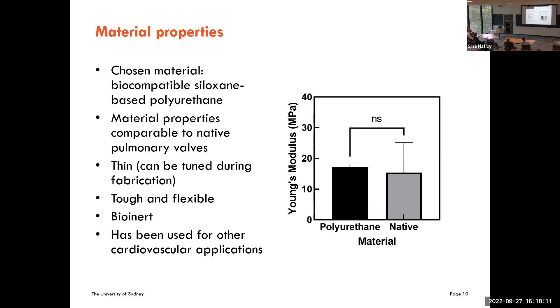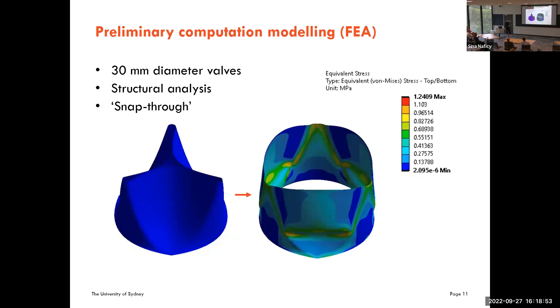The chosen material is a biocompatible and biostable siloxane-based polyurethane. Mechanical testing showed material properties comparable to native pulmonary heart valves. Thickness is tunable during fabrication — thinner or thicker as needed, within limits. It is a tough yet flexible bio-inert material that has also been used for other cardiovascular applications.